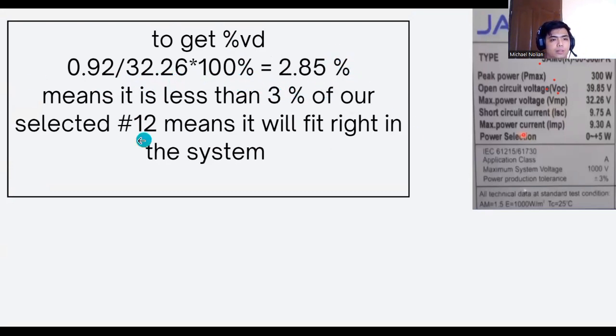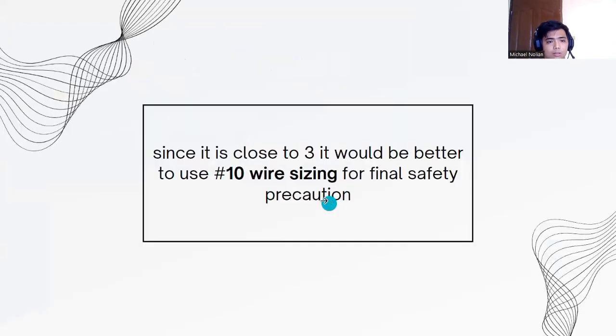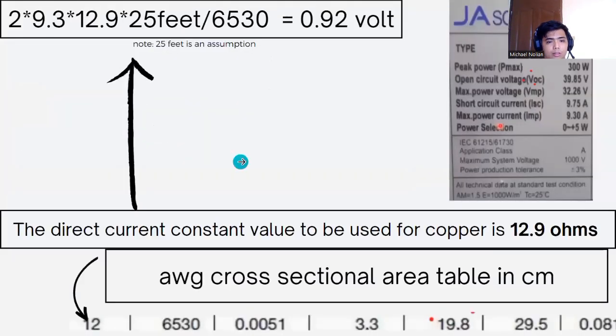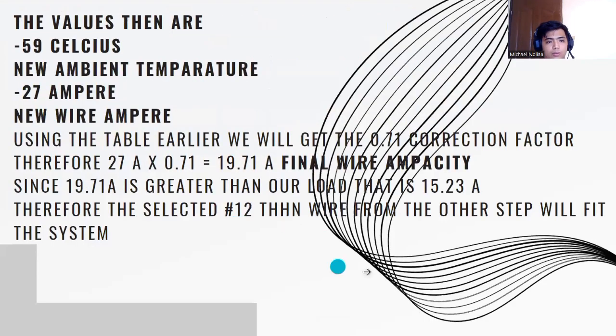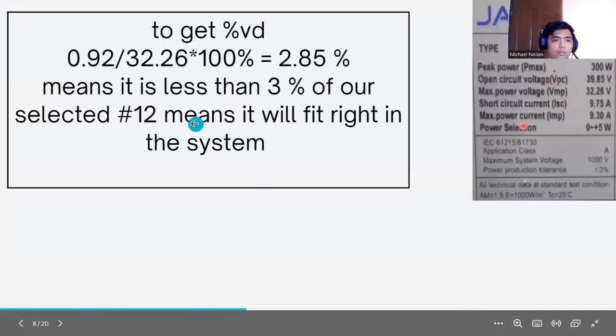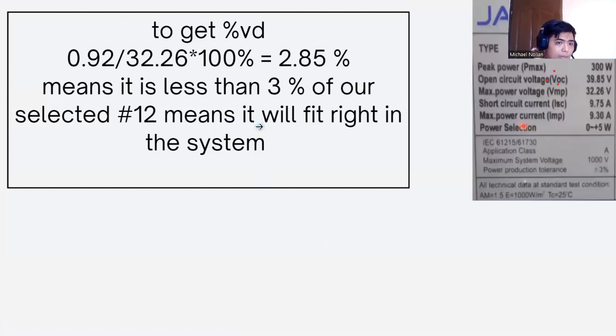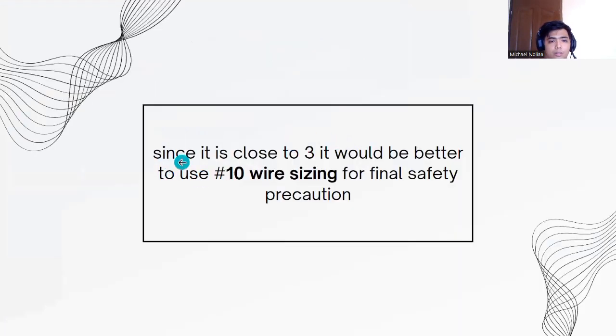It is just basic math, no transposing or anything else. So this means the drop is less than 3% when we selected the 12 THHN from earlier, which means it is fine for the system. But it is quite close to 3. Since it is close to 3, it will be better to use the size 10 wire as a final safety precaution.